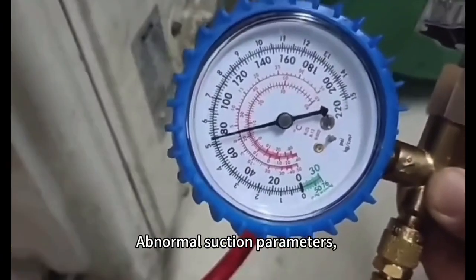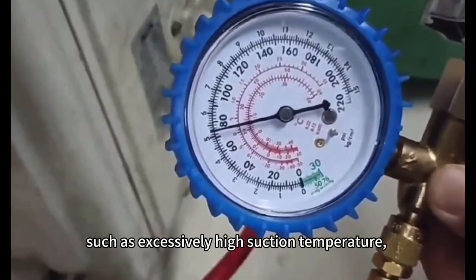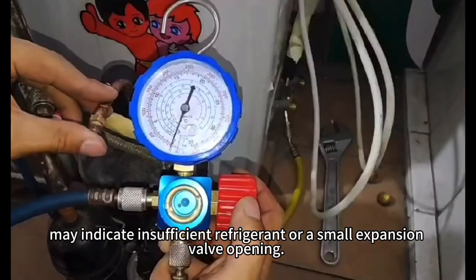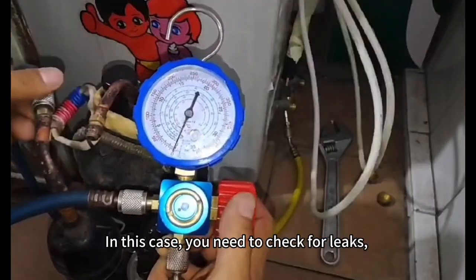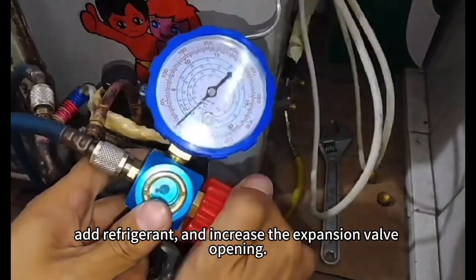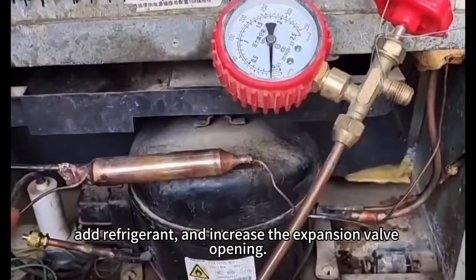Abnormal suction parameters, such as excessively high suction temperature, may indicate insufficient refrigerant or a small expansion valve opening. In this case, you need to check for leaks, add refrigerant, and increase the expansion valve opening.